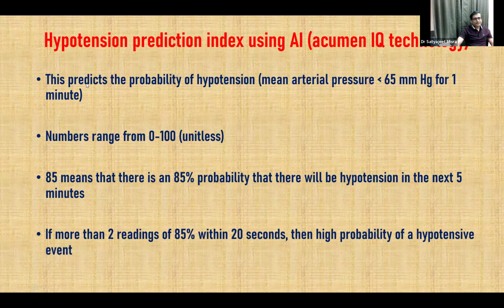So what the HPI does is it predicts the probability of hypotension, and the algorithm defines this as a mean arterial pressure of less than 65 millimeters of mercury for 1 minute. And it gives us values from 0 to 100. These values are unitless. The higher the value, the higher the probability of the patient developing a hypotensive event in the next few minutes. So if the number reads 85, that means there's an 85% probability of hypotension in the next 5 or so minutes.